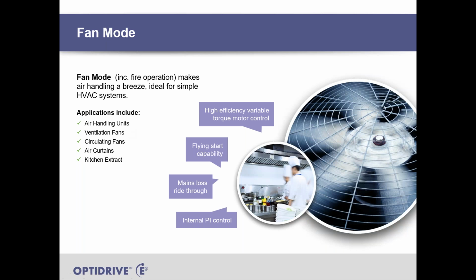In fan mode, we also have, in addition to the internal PI controller, flying start capability. So with fans, even when the fans are turned off, if there's airflow in the air ducts, then they can actually push the fan to run in the opposite direction. So what we do, we can actually synchronize with an already spinning fan and slow it down or speed it up or change direction, whatever is needed, so that we don't have a big mechanical shock when we try and start it from zero.